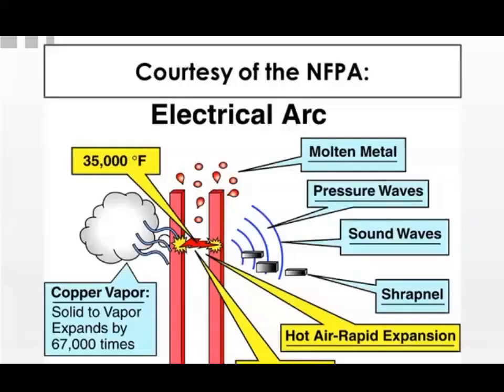Okay, this pictographic, courtesy of the National Fire Protection Association, does a very good job of highlighting the hazards. And I encourage you, after this presentation, and due to time constraints I'm not able to do it now, to just search YouTube for arc flash events, and you will see how suddenly and severely this occurs. This happens in milliseconds. I've done training, and believe it or not, some electricians argue with me saying, well, I've been doing this for 25, 30 years. This would never happen to me. Well, that's that complacency factor kicking in. And you don't have to actively do something for an arc flash event to occur. You can just be walking by a piece of equipment and an arc occurs, and without even touching the equipment, one of these can occur.